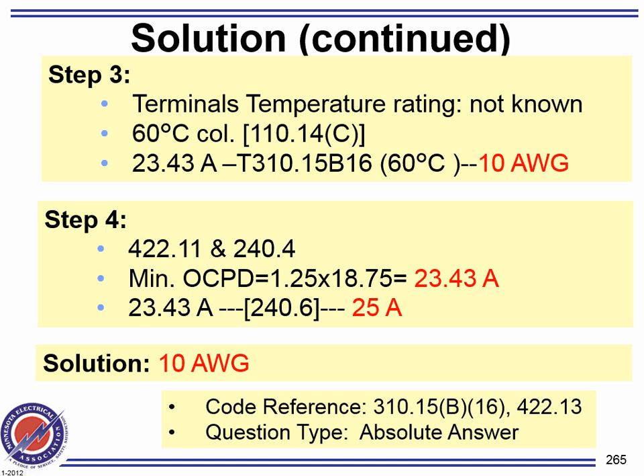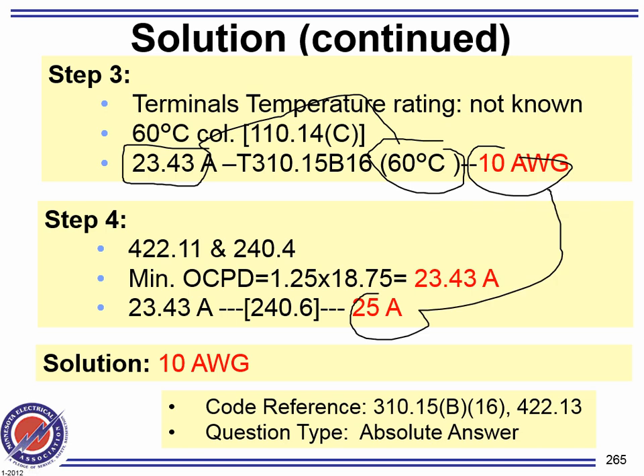So 23. Now, when you find the conductor, the amps for the conductor 23, why did we go to this column? Yes, less than 100. That'll give me number 10. So number 10 and 20 amp. Have I exceeded the small conductor rule? No, because number 10, you can go as high as 30 amps in it, as high as 30 amps. Any comments, gentlemen, questions?